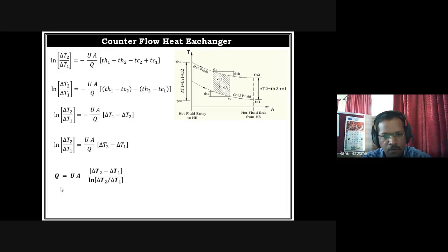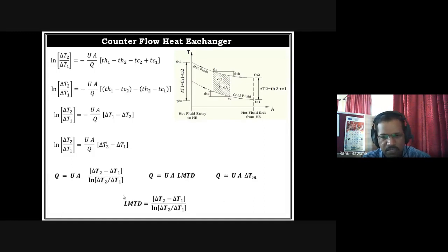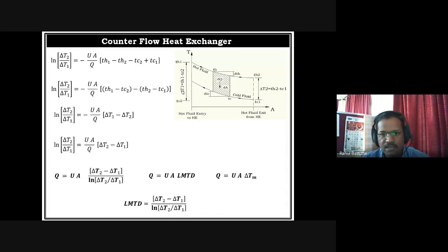Using the regular form Q = U × A × LMTD, where LMTD is the logarithmic mean temperature difference (also written as ΔTm), the LMTD for a counter flow heat exchanger is: LMTD = (ΔT2 − ΔT1) / ln(ΔT2 / ΔT1). The notation and formula are the same as for parallel flow, but during calculation ΔT1 is different: for counter flow ΔT1 = TH1 − TC2, while for parallel flow ΔT1 = TH1 − TC1.